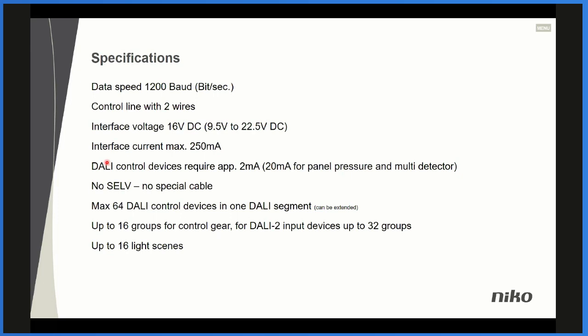Each time you put one device on the DALI bus, it could be a luminaire, it consumes up to 2 milliamps in general. If you have a multi-detector or whatever, it consumes a little bit more. So we have to calculate that it's okay. You will never exceed the 250 milliamps normally. That's not the limitation. The limitation is the number of luminaires that could be on one DALI bus.